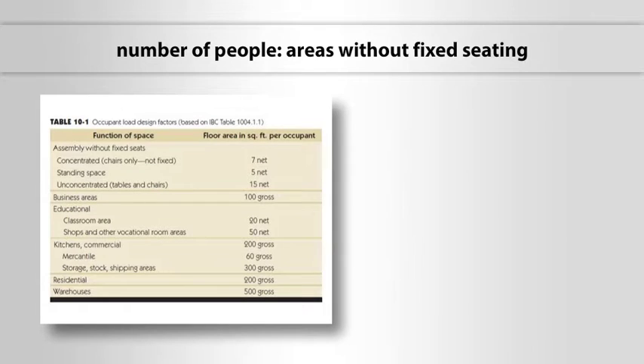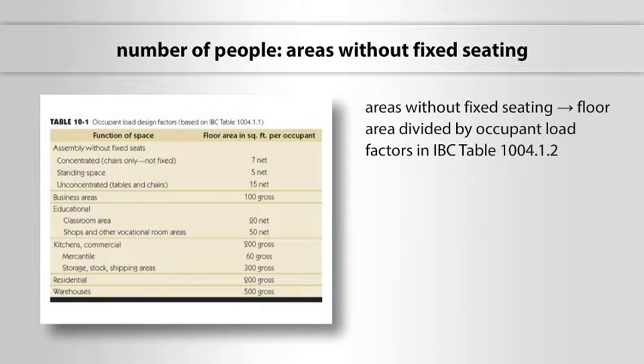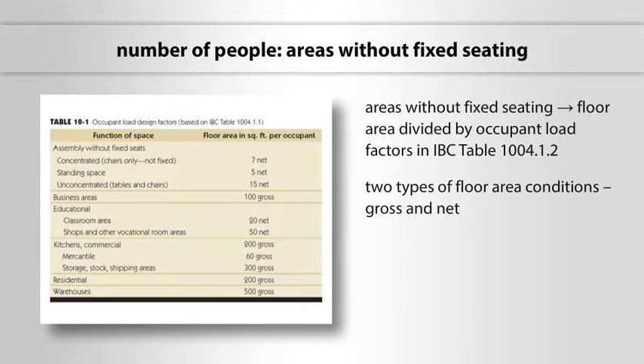The design occupant load in areas without fixed seating is calculated by taking the floor area and dividing it by the occupant load factors in IBC table 1004.1.2. A sampling of this table is shown in this image. The table has two different types of floor area conditions, gross and net.